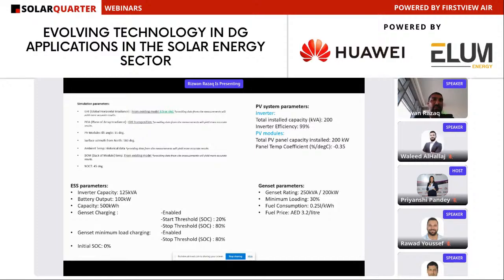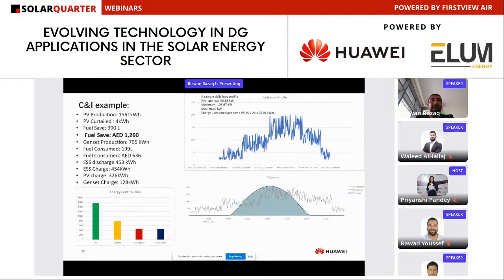And then from the energy storage parameters perspective, around 125 kVA battery, with an output of around 100 kilowatts, and the capacity for the energy storage is around 500 kilowatt hours. Other factors to consider from the energy storage perspective are your state of charge and the state of health, and these factors need to be considered correctly in your total calculation. Now, there are multiple different software packages available from the hybrid controller companies like Elum as well. And here is just one example, taken from the top right-hand side, the current daily load profile.